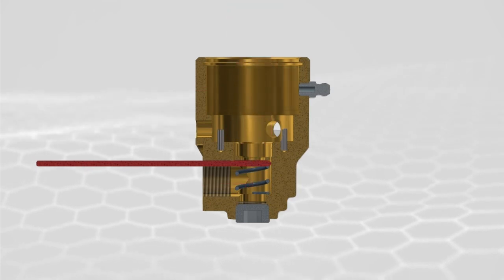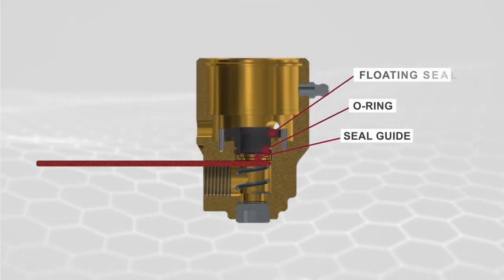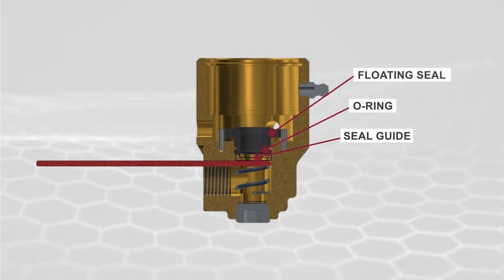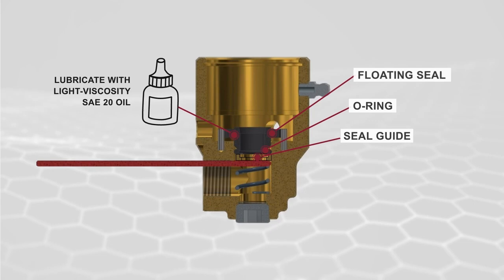Remove the spring compressor, insert the seal guide, then grease and insert the o-ring. Install new floating seal after cleaning the seal face and lubricate it with light viscosity SAE 20 oil.